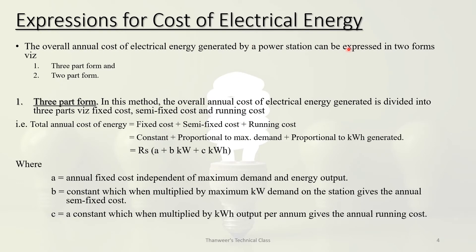The expression for the cost of electrical energy uses a three-part form. The total annual cost of energy is divided into: fixed cost, semi-fixed cost, and running cost. In the three-part form, the cost of energy is proportional to maximum demand and to kWh generated. Maximum demand can be expressed in kW, kVA, or kVAr — as seen in the power triangle.